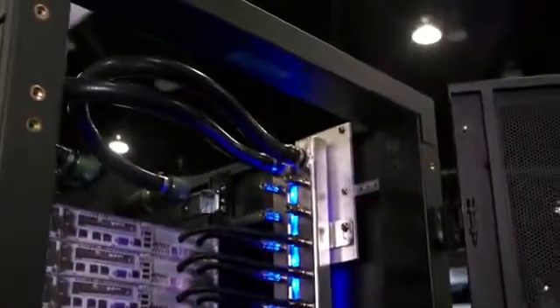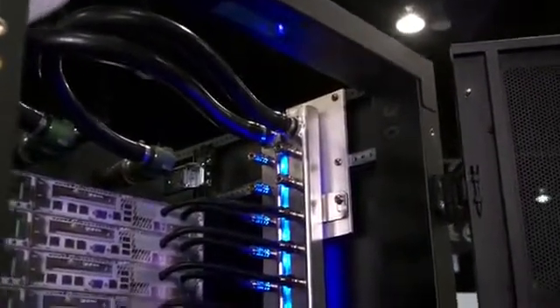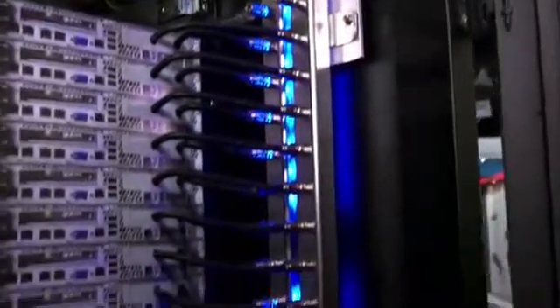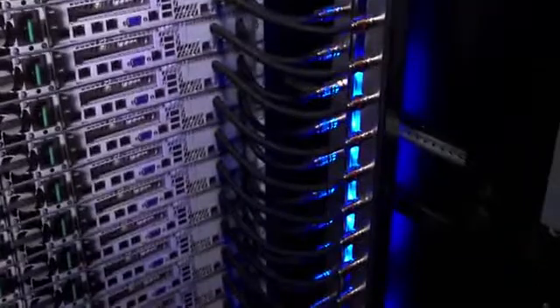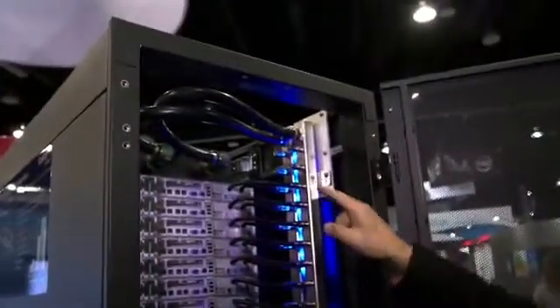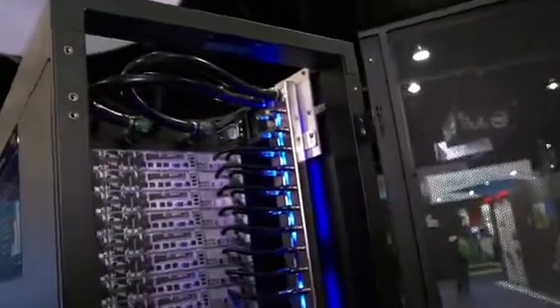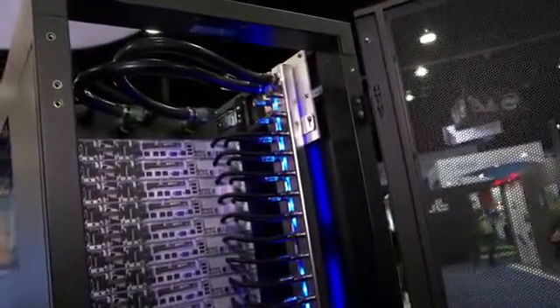Into our heat dissipation modules. So you'll notice I'll use the word module quite a bit because we've got natural breakpoints here. We do the server modules, which is what we looked at before, going into the manifold module, bringing that heat up, and then in this example we have our CHX, which we call a coolant heat exchanger. The coolant heat exchanger then dissipates all the heat into a facility water flow and outside to a dry cooler or a cooling tower, or in some cases a chilled water supply.